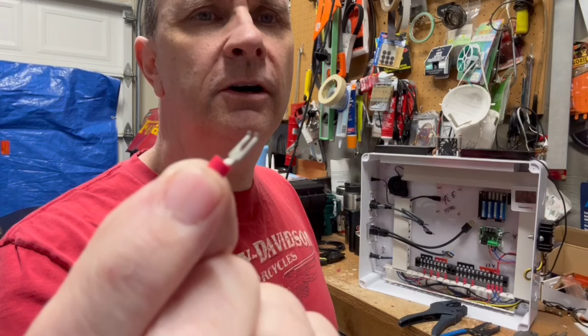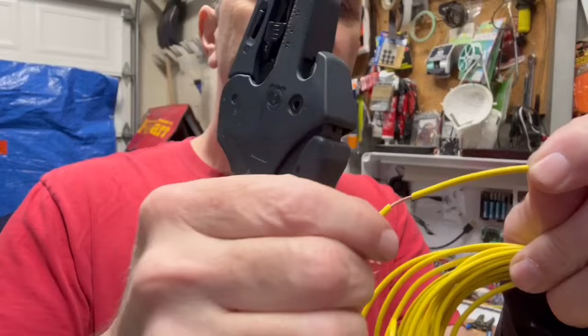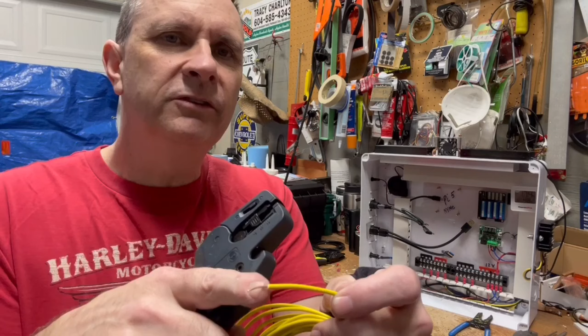The other thing I wanted to show you is that a lot of people use a regular wire stripper. You can use these, they're okay, but nowadays pretty much everybody uses an automatic wire stripper. Just insert the wire to the depth you want, hit it, and it automatically strips for you. It never cuts a strand, which matters because cutting a strand reduces the capacity of your wire. If you use the wrong size on a manual stripper, you can break off 6 or 8 strands, really cutting down the capacity. So use the automatic stripper.